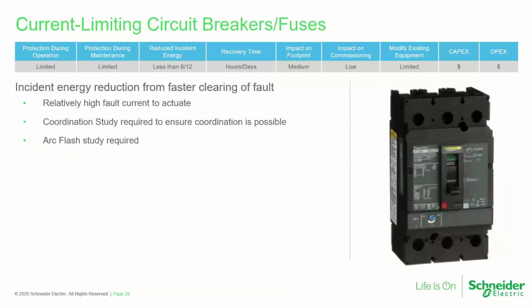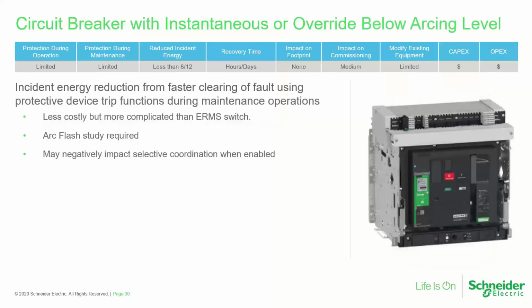Current limiting circuit breakers or fuses are certainly very good for systems with high levels of fault current available. The last one, circuit breakers with instantaneous overrides below the arcing fault current in the system. This is one of the solutions that is listed in NEC 240.87, so we kind of addressed that. Less costly but more complicated than an ERMS switch or maintenance switch. Why do we say it's more complicated?